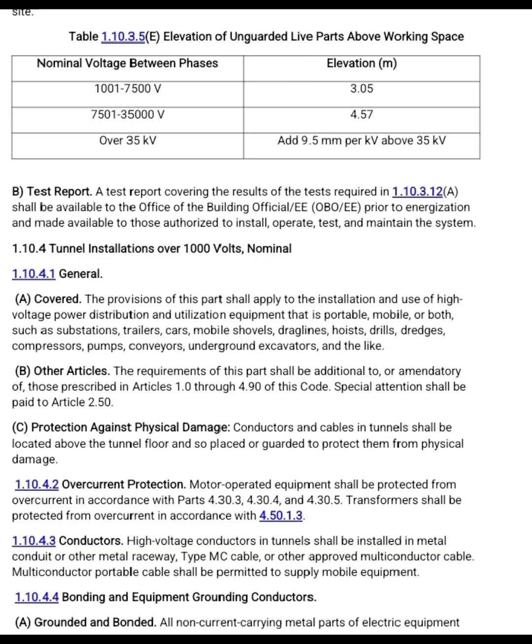1.10.4 Tunnel installation over 1000 volts nominal. 1.10.4.1 General. A. Covered. The provisions of this part shall apply to the installation and use of high voltage power distribution and utilization equipment that is portable, mobile, or both, such as substations, trailers, cars, mobile shovels, draglines, hoists, drills, dredges, compressors, pumps, conveyors, underground excavators, and the like. B. Other articles. The requirements of this part shall be additional to or amendatory of those prescribed in Articles 1.0 through 4.90 of this code. Special attention shall be paid to Article 2.50.